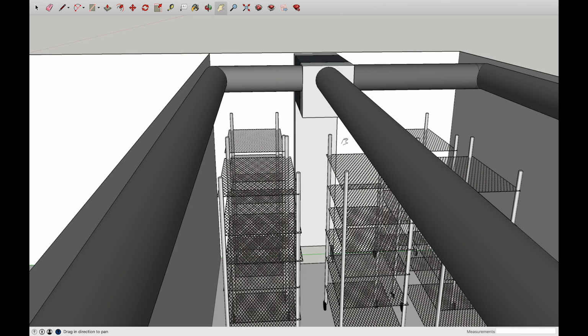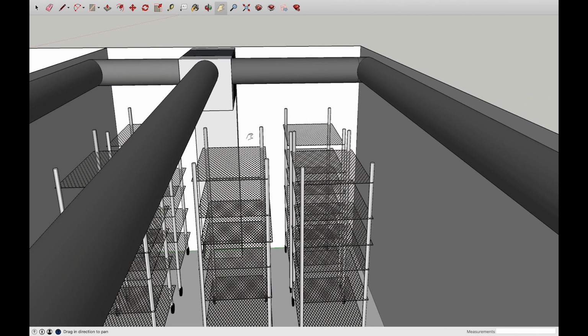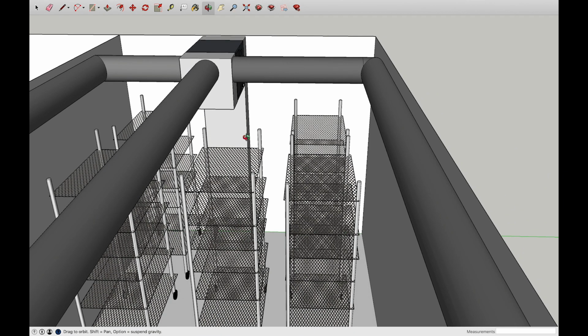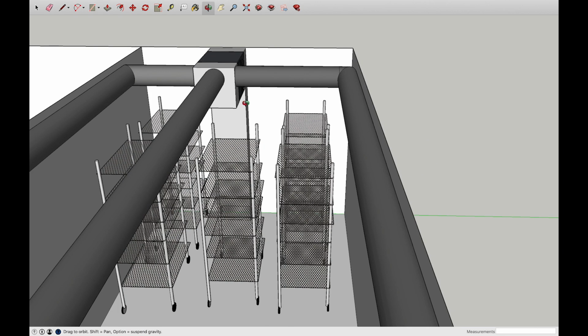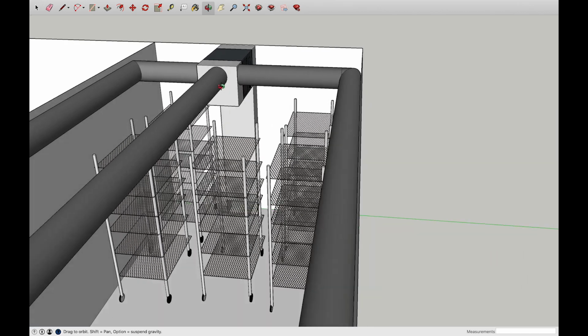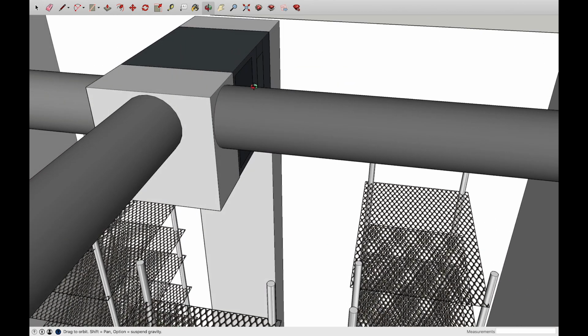The standard rule of thumb is if we're looking to have, say, 20 pounds of dry product in the space, which is calculated based off your flower lights and how many pounds per light, for every 20 pounds there's going to be about 80 pounds roughly of water. Once we know that water weight, we can then select the proper size system. For the most part, the 2-ton Evolution hits most of them, unless you're going into a significantly oversized, sea of green type application, where you're having 100,000 square foot open continuous space, then you might want to go up into something larger or multiples.